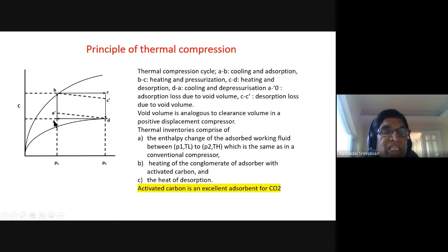So the compression cycle we have is A, B, C, D. We can take A to B as equivalent to suction in a conventional compressor. BC is the compression. CD is the discharge from the compressor. And DA can be taken as the re-expansion. In a compressor there are four processes: suction, compression, discharge, and re-expansion. So ABCD represents, or is analogous to, that.